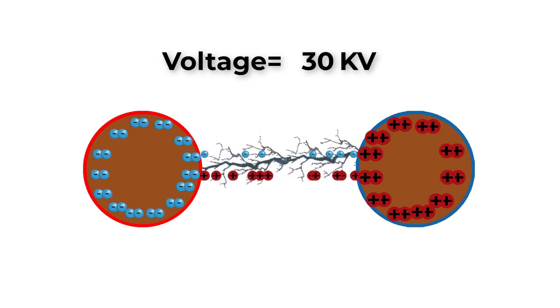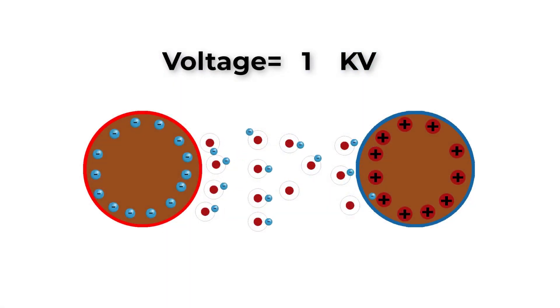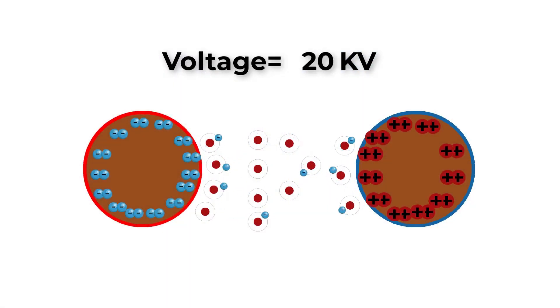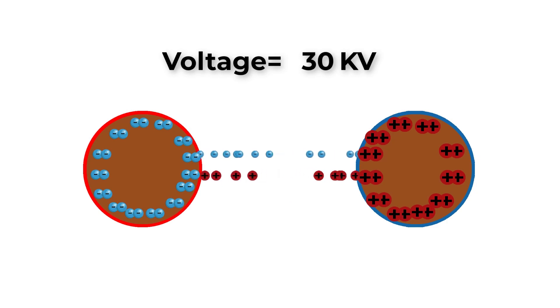The ionized air results in electric discharge around the conductors due to the flow of these ions. This gives rise to a faint luminescent glow, along with a hissing sound accompanied by the liberation of ozone. If the voltage across the lines continues to increase, the glow and hissing noise becomes more and more intense, inducing a high power loss into the system.